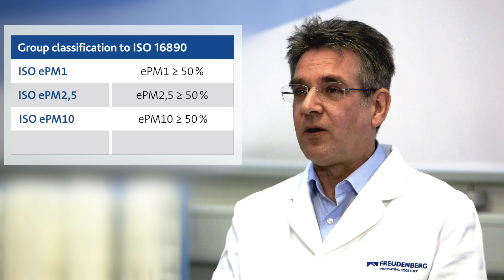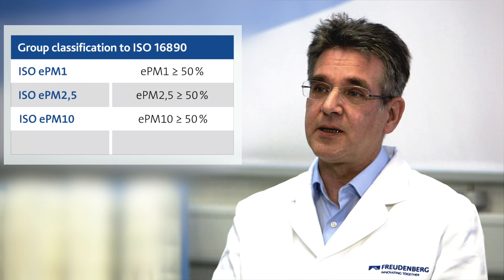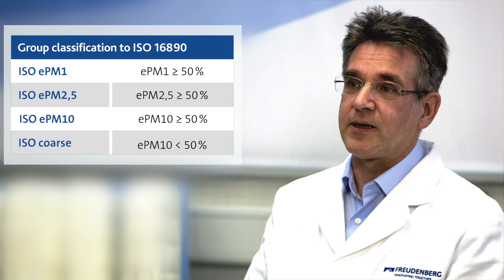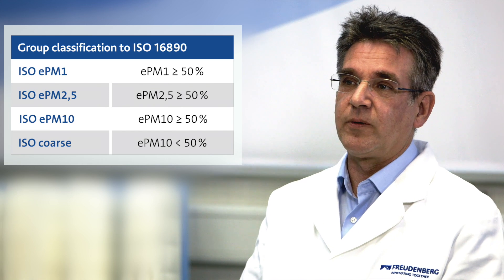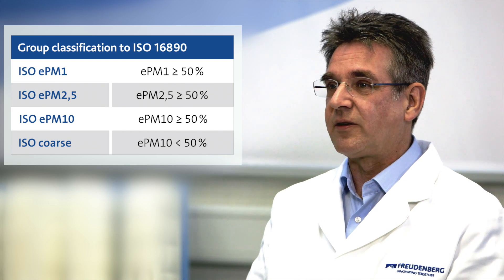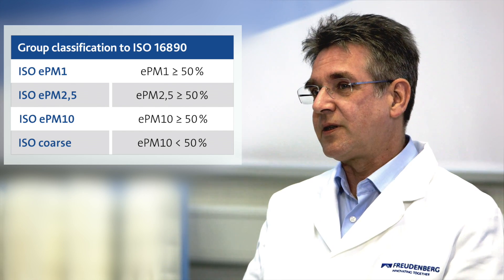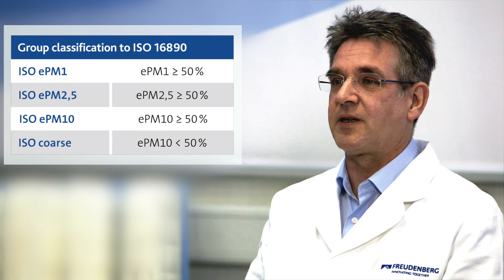The new ISO standard will also rate coarse dust filters. They will be grouped as ISO Coarse, and together with that, we will report the initial gravimetric arrestance to a synthetic test dust, the so-called AC fine dust.